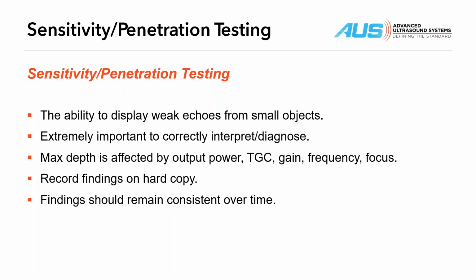So if you come do a PM in January and you go back in July, you want to make sure you're using the same output power. The TGCs are relatively the same. Your gain is the same. Your frequency, you're using the same frequency. And you're looking at things the same way, basically. So you don't want to compare apples to oranges. You want to be apples to apples, right? And that's really the important thing, is be very pointed and very objective about how you're setting the system up, being very consistent.